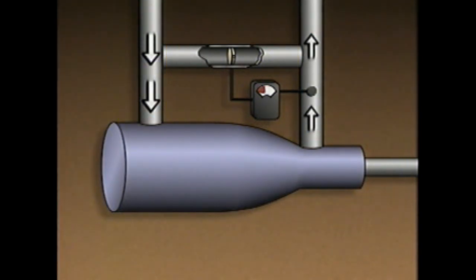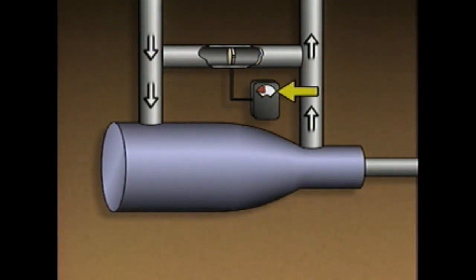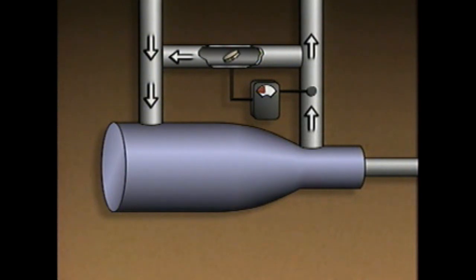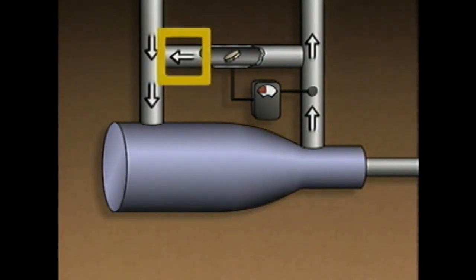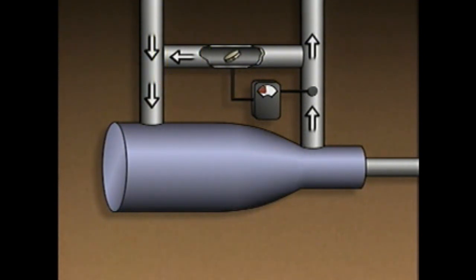When low demand causes the gas flow rate to approach the surge point, the flow sensor sends a signal to the flow controller. The controller then opens the recirculation valve and routes a portion of the discharge gas flow back into the suction piping. When a portion of the discharge gas flow is routed back into the suction piping, the gas flow through the compressor increases and it stays above the surge point.